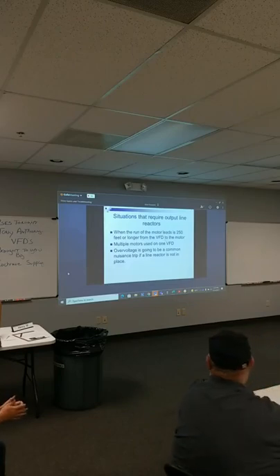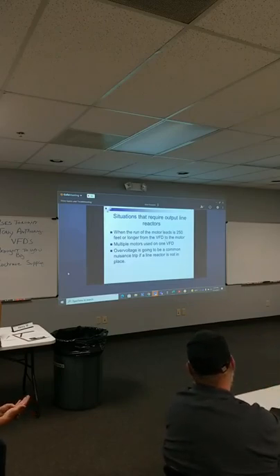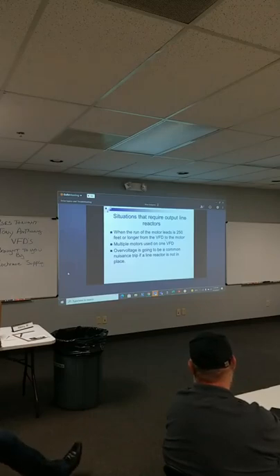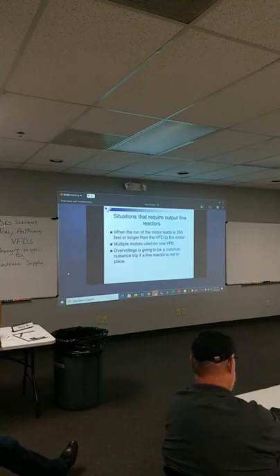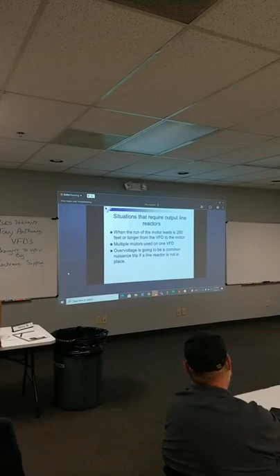And we recommend a load reactor at that point, because even though they're the same motors, and we're sending them the same frequency and the same voltage, because of mechanical differences there'll be a slight difference in speed. It may be a half RPM, but that can cause some voltage feedback into the drive sometimes. It doesn't usually, but occasionally it will, and cause problems. One thing you can do to mitigate that is put a load reactor on there. So if you're running more than one motor on a drive, especially more than two or three, then we recommend you put a load reactor there. If you're getting some overvoltage nuisance trips and you've got several motors on one drive, you probably need a load reactor out there.